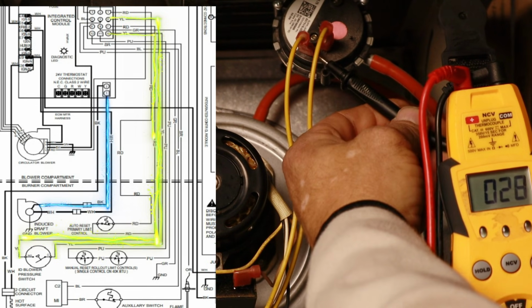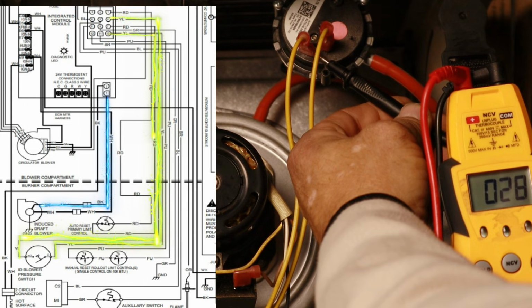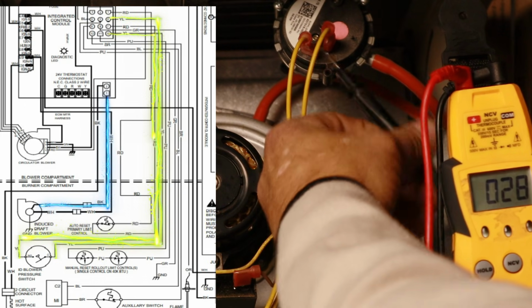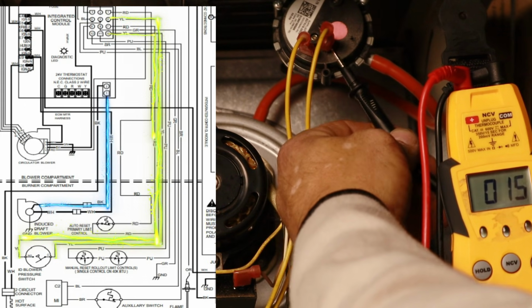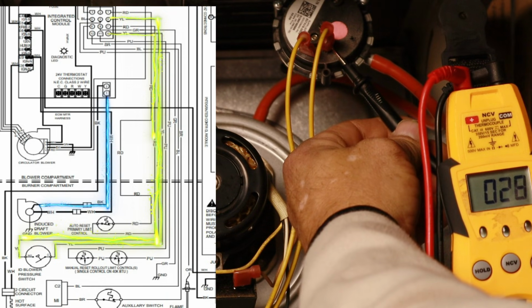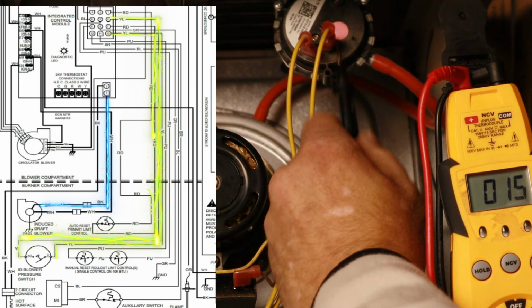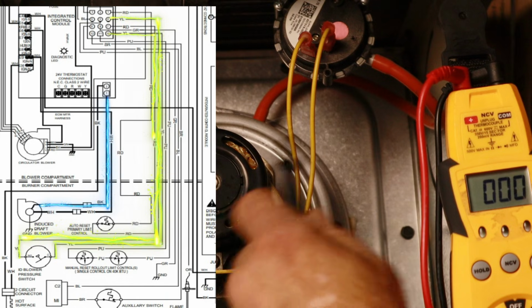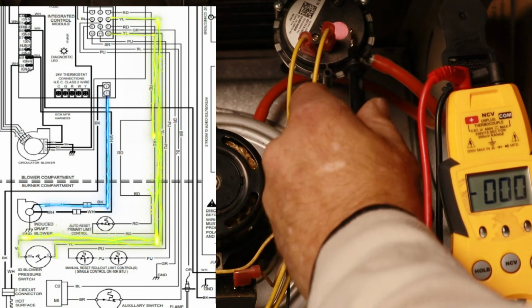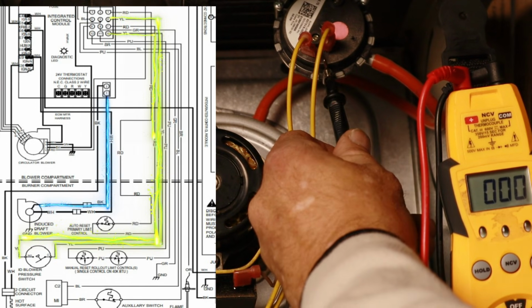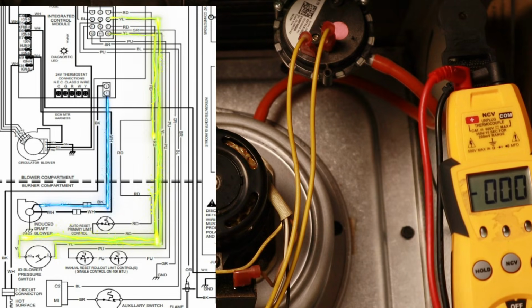you can see I'm reading my 28 volts. And to make sure the pressure switch is working, I'm going to go and test the other side of that switch, and I also have 28 volts. So I know my pressure switch is working. My inducer motor is creating a draft that's pulling in that diaphragm, closing that switch, and allowing the 24 volts to travel through.